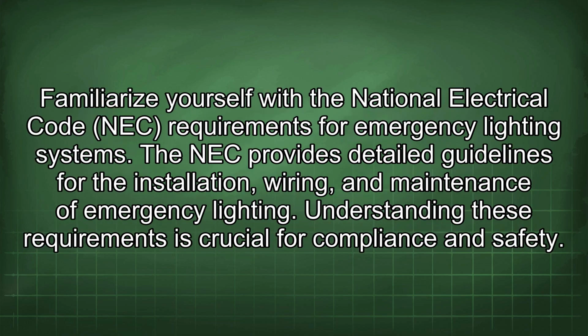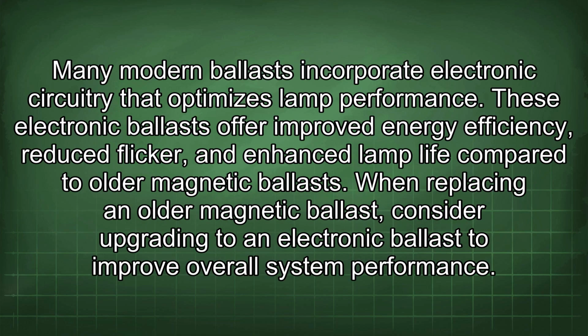Familiarize yourself with the National Electrical Code (NEC) requirements for emergency lighting systems. The NEC provides detailed guidelines for the installation, wiring, and maintenance of emergency lighting. Understanding these requirements is crucial for compliance and safety. Many modern ballasts incorporate electronic circuitry that optimizes lamp performance. These electronic ballasts offer improved energy efficiency, reduced flicker, and enhanced lamp life compared to older magnetic ballasts. When replacing an older magnetic ballast, consider upgrading to an electronic ballast to improve overall system performance.